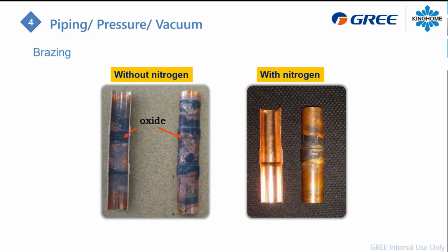The refrigerant will act as a kind of solvent, so it will dissolve and powder the oxide. You will not see big chunks of scale in the system; it will create just a small powder, some residue. That residue may not be a problem from the start, because the strainer will hold that kind of powder, but if it hits the EEV, it will be really hard to service the unit, and that will cause you big trouble.